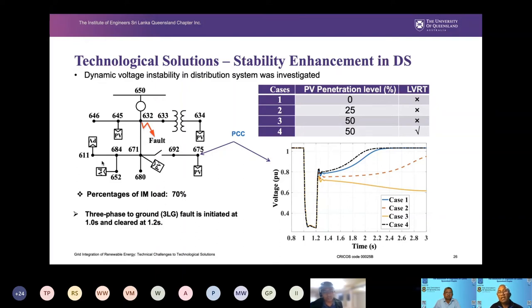When it comes to solutions, as I mentioned, there are different types of problems at the transmission level and the distribution level. Here we are looking at one of the distribution level instability problems. We are trying to find the solution within the technology itself by having better control. We did this study in a test system. We ran a number of different cases: 0%, the normal business as usual case, 25% penetration, case 2, 50% penetration. Case 4 was 50% penetration with the so-called low voltage ride-through capability. If we don't have this capability, the dark dotted line, we will have a problem.